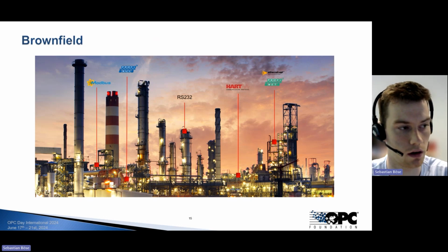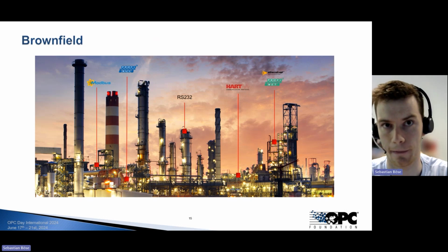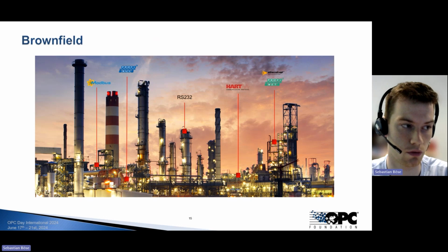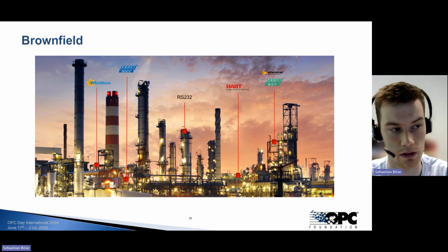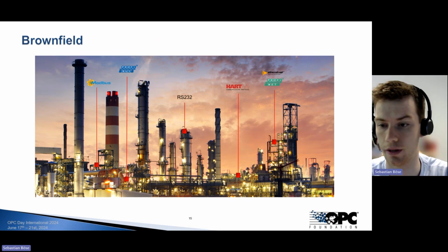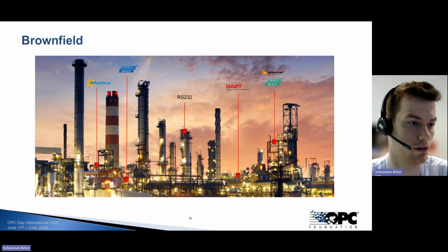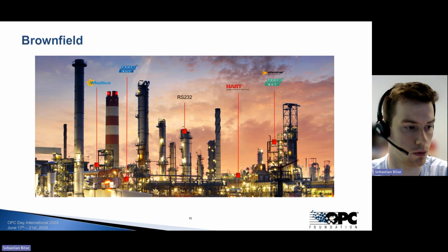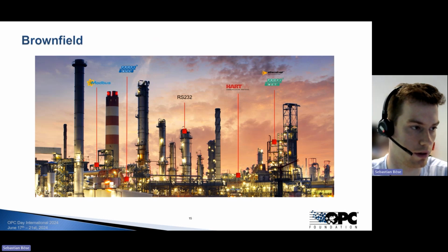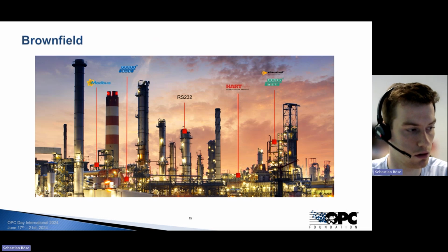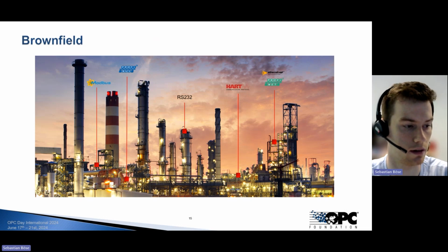I mean, some of them like RS232 don't give us that much information that we can access out of the field device. Via HART, it's more or less all of the data in the PADIM that we can fill. And it's the same with Ethernet APL and Profinet. So there is more and more data available than via RS232, for example. But the main message is that we can access all of this and get a benefit out of that, but only if we do it in a standardized way with a standardized information model.